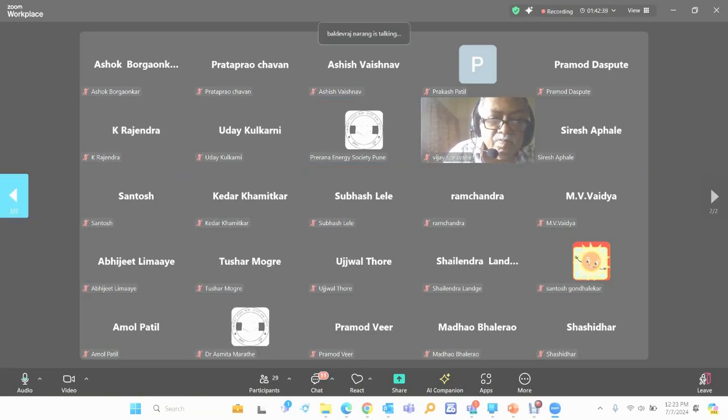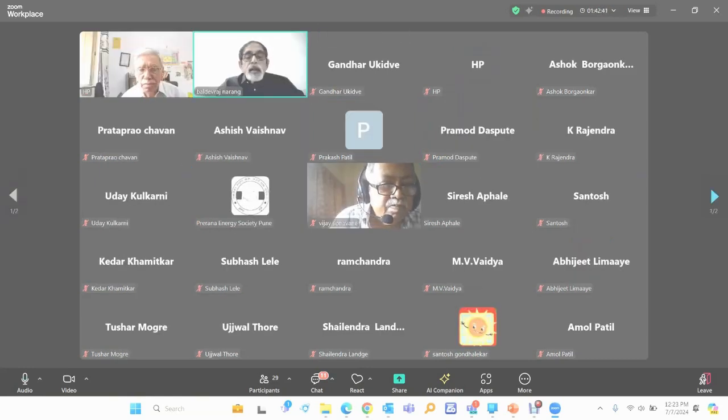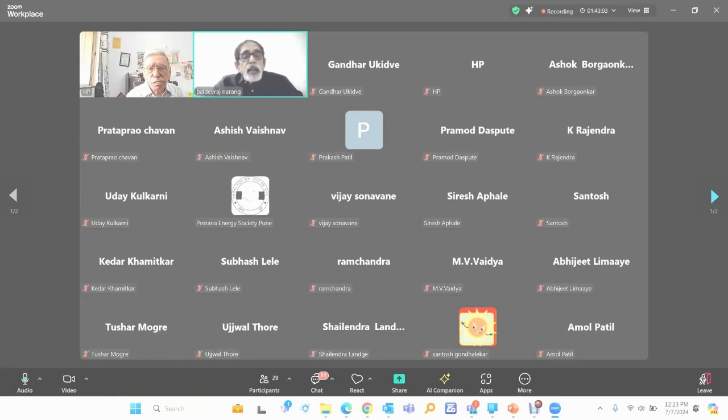The reactor and active filter. A reactor is a part of the passive mitigation system. Passive harmonic mitigation is done by the reactor. It has limitations. We are normally targeting mainly one harmonic at a time, say 7% or 5.69%. When we put a reactor, we take care of mainly the fifth harmonic and to some extent the seventh harmonic and higher order harmonics. But it is very limited.